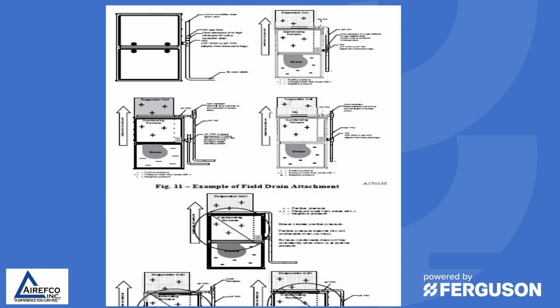So we mentioned condensate management. You need to make sure that when you're running your condensate off a furnace or an air conditioning coil, you run it according to the manufacturer's specifications. Many tests have been run on modern coils and modern furnaces to find the positive and negative positions and how to best drain the condensate out of the air conditioning coil and the furnace itself. So make sure that you consult the installation guide for diagrams like this that show you the ways that you can run the condensate and the ways that you should not.